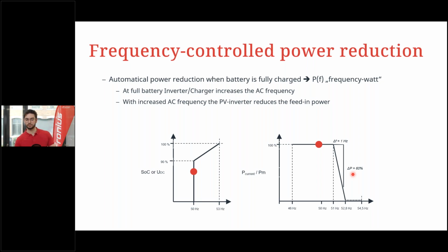And with the frequency controlled power reduction, we have an automatic increase of the frequency as soon as we come to 100% state of charge of the battery. This is done by the inverter charger from Victron itself. It measures voltage and current of the battery, and then it can indicate, okay, we are nearly 95% state of charge of the batteries, which means I need to increase the frequency by a little.